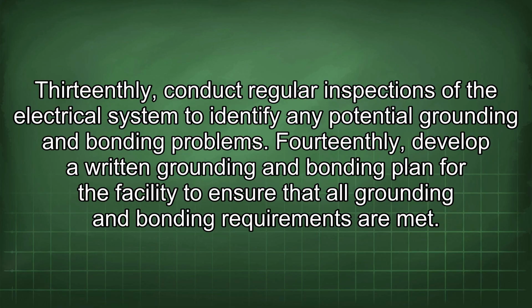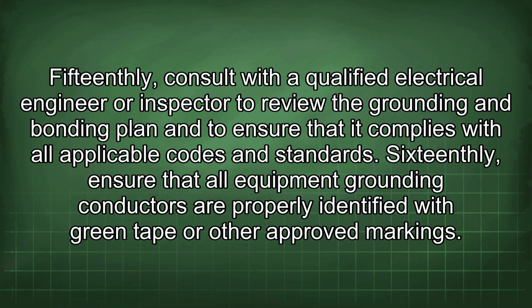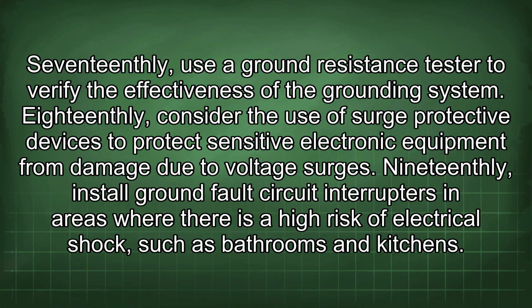14thly, develop a written grounding and bonding plan for the facility to ensure that all grounding and bonding requirements are met. 15thly, consult with a qualified electrical engineer or inspector to review the grounding and bonding plan and to ensure that it complies with all applicable codes and standards. 16thly, ensure that all equipment grounding conductors are properly identified with green tape or other approved markings. 17thly, use a ground resistance tester to verify the effectiveness of the grounding system.